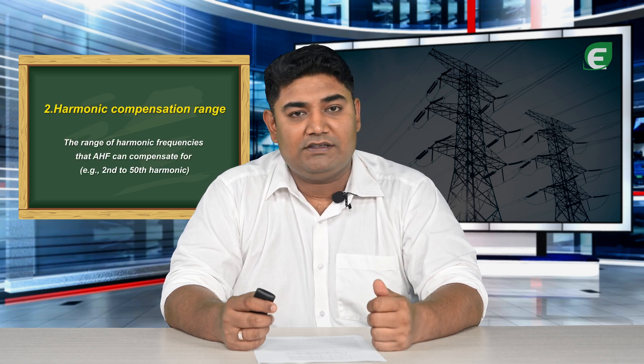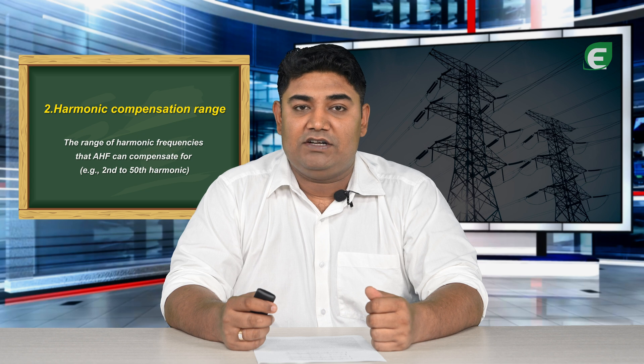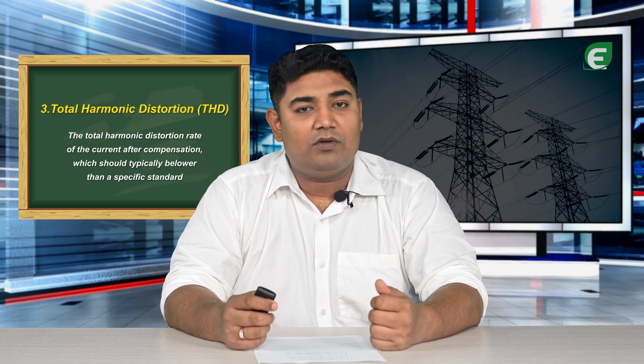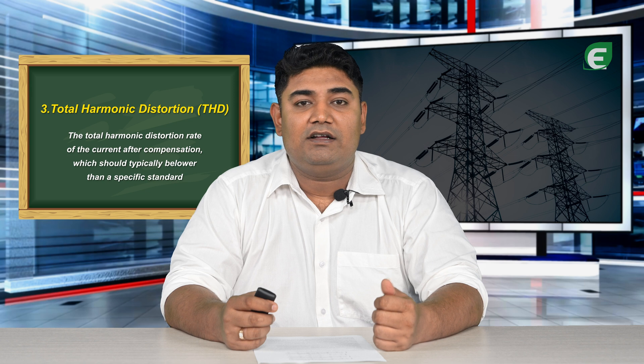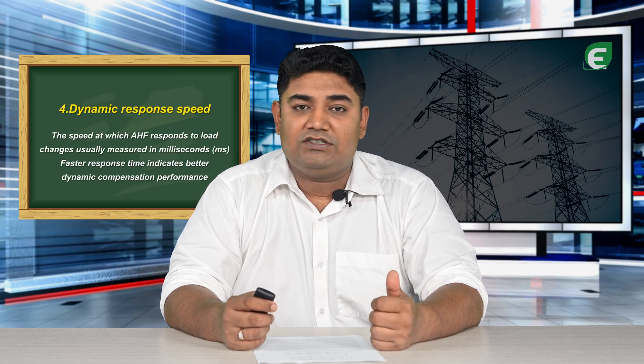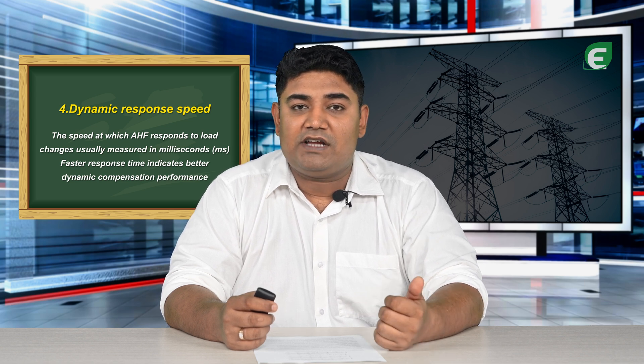Harmonic compensation range is the range of harmonic frequencies that AHF can compensate for. The total harmonic distortion rate of the current after compensation should typically be lower than a specific standard. The dynamic response speed is the speed at which the AHF responds to load changes, usually measured in milliseconds — a faster response time indicates better dynamic compensation.